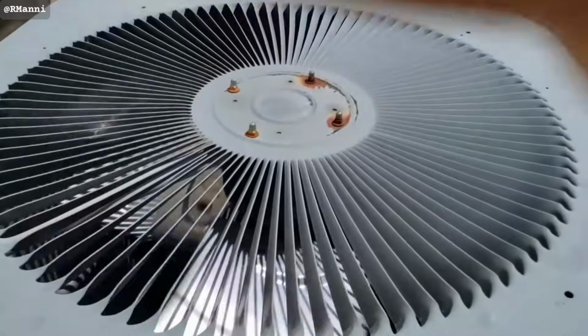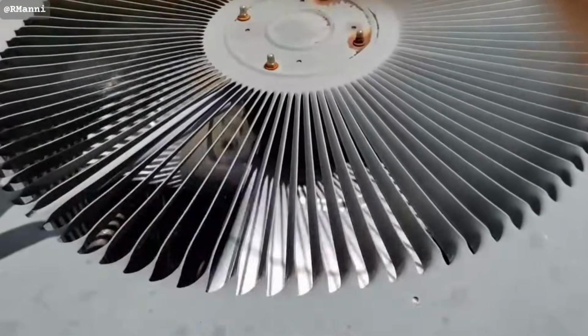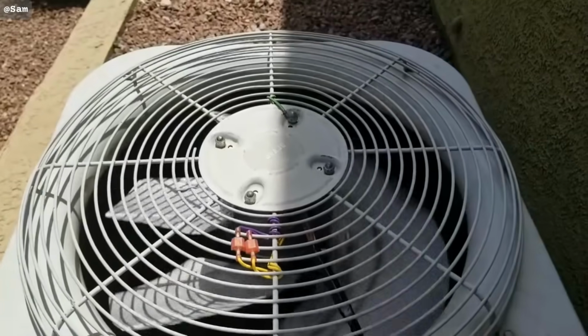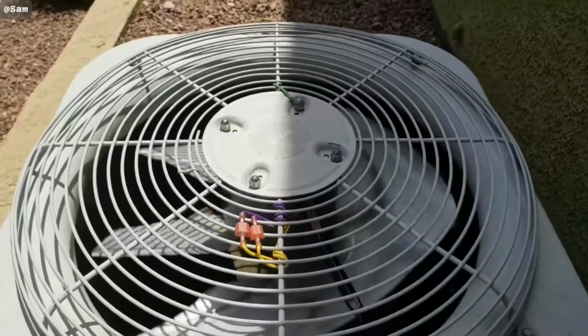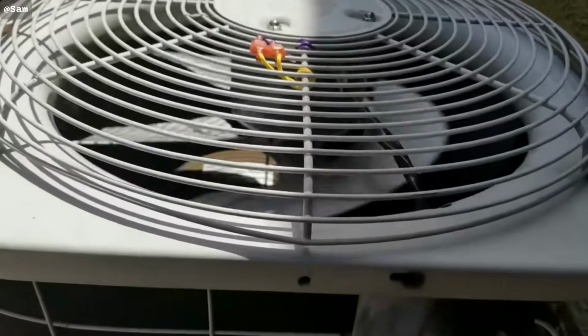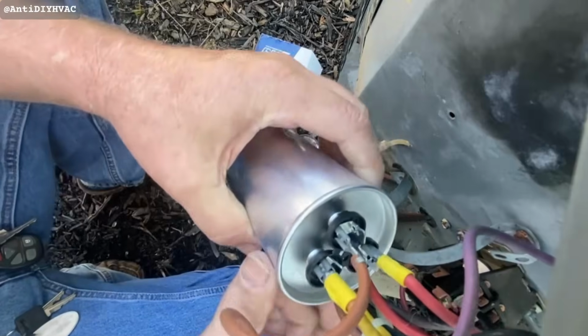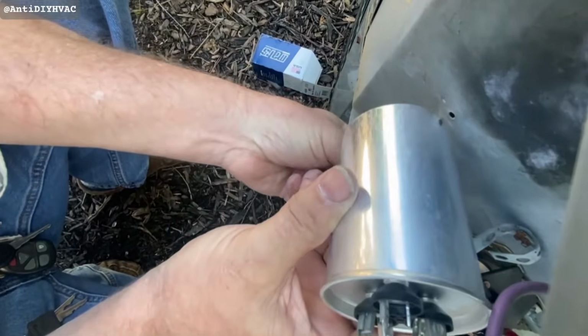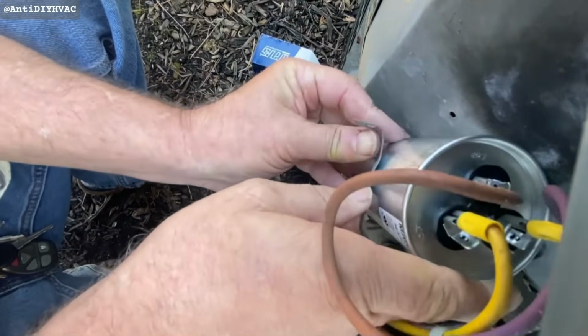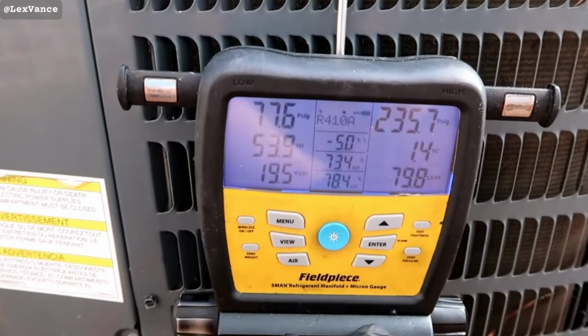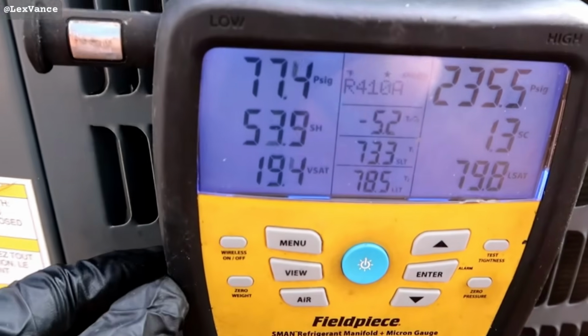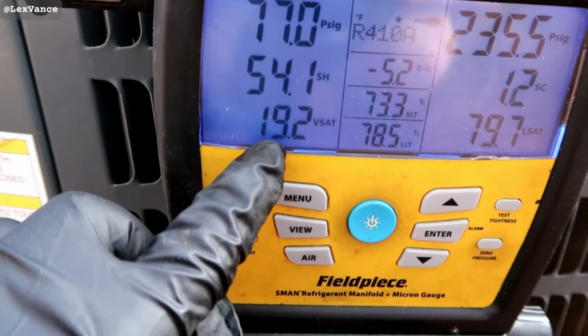Now for what I deliberately don't do. This is the part of the video that gets me arguments in the comments. I don't deep clean my blower wheel every year. If it's running quiet and the temperature split is in range, I leave it alone. I've talked to too many techs who threw a wheel off balance by aggressive cleaning and created a vibration problem that wasn't there before. I don't run my filter at MERV 13 or higher.